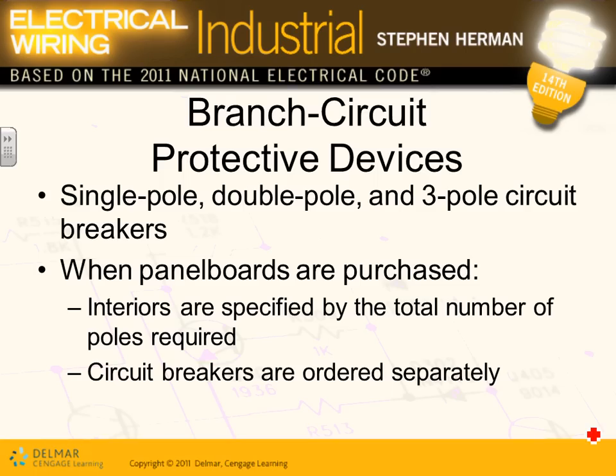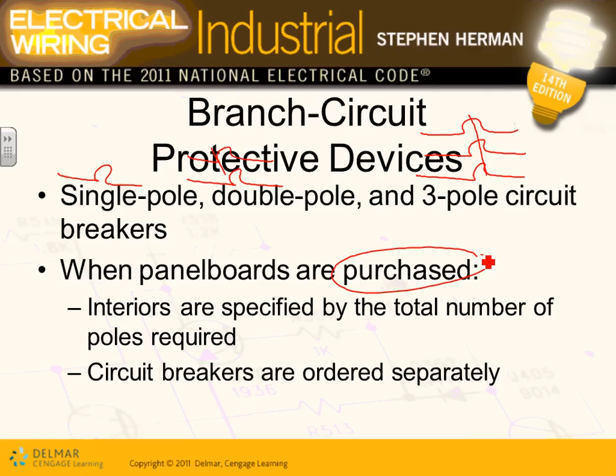or cable connectors. Circuit breakers, Adam, can come as a single pole like this, or as a double pole like this, or as a 3-pole like this. These are all circuit breakers, and you guys are very familiar with that. Single pole, 2-pole, or 3-pole circuit breakers. When you purchase the panel, Adam, you have to specify the interior of these panels, the total number of poles you have, and the type of the poles. How many 20 amp single pole, and how many 30 amp or 20 amp 2-pole, and how many 50 amp or 40 amp single pole, 2-pole, or 3-pole. And then you separately order your circuit breakers.